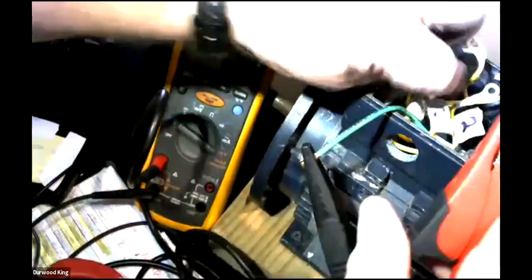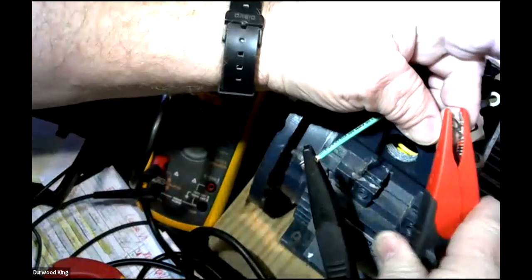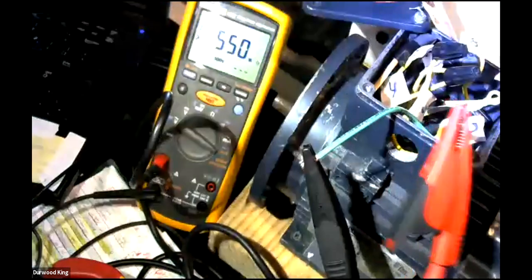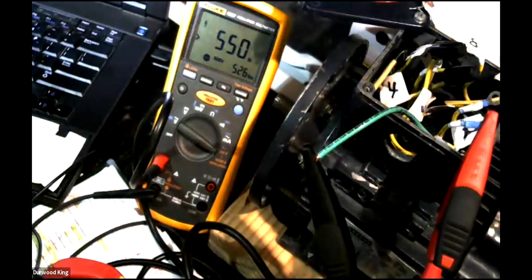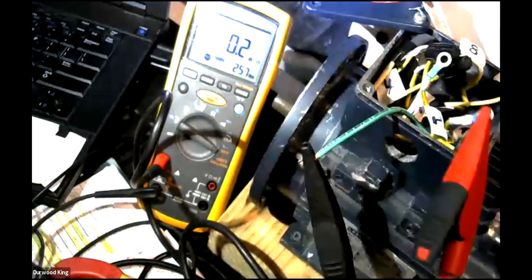Now, let's put our ground on, and then let's go to line 1. Now you look close at this here now. Ground in line 1, I'm going to hit my button to watch. What does it say? Greater than 550. Greater than 550. Let's go to line 2. See that? Line 2 is bad. So this meter picked that up. It picked up that it's bad.